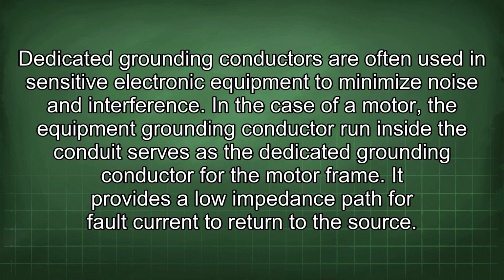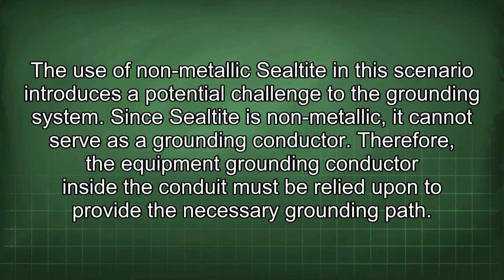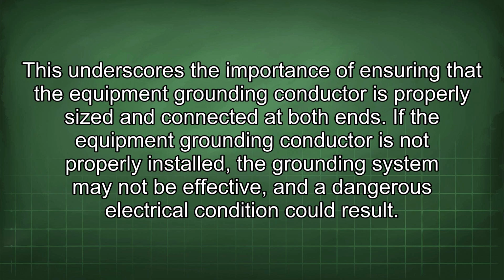In the case of a motor, the equipment grounding conductor run inside the conduit serves as the dedicated grounding conductor for the motor frame. It provides a low impedance path for fault current to return to the source. The use of nonmetallic Sealtite in this scenario introduces a potential challenge to the grounding system. Since Sealtite is nonmetallic, it cannot serve as a grounding conductor. Therefore, the equipment grounding conductor inside the conduit must be relied upon to provide the necessary grounding path. This underscores the importance of ensuring that the equipment grounding conductor is properly sized and connected at both ends.